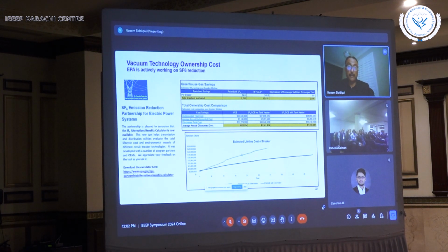There are several tools globally available which can calculate the total ownership cost comparison between SF6 breaker and vacuum clean air breaker. On this page, on the bottom left, you can see one EPA US agency. They have a calculator on their website. You can download a simple Excel sheet, put in some parameters of your utility or company, and see if you have 10 breakers or 50 breakers, you can calculate the overall comparison of ownership cost between these two technologies.